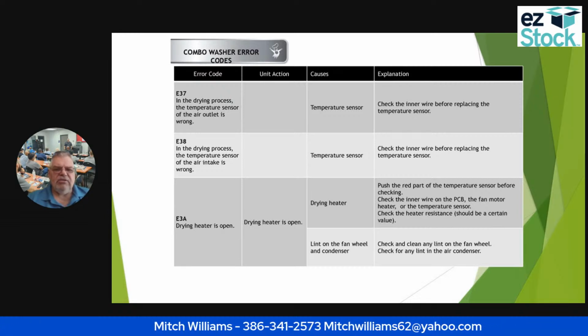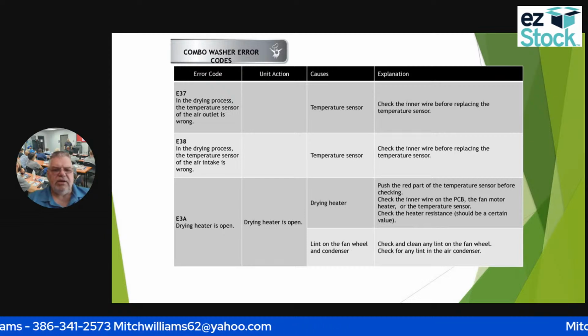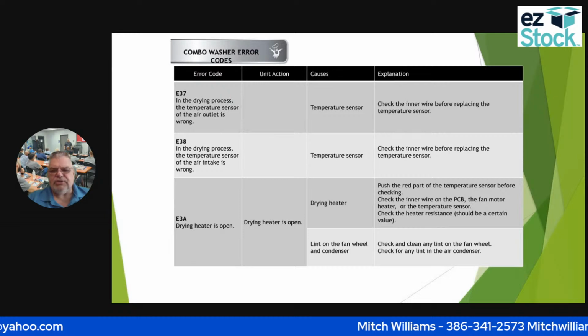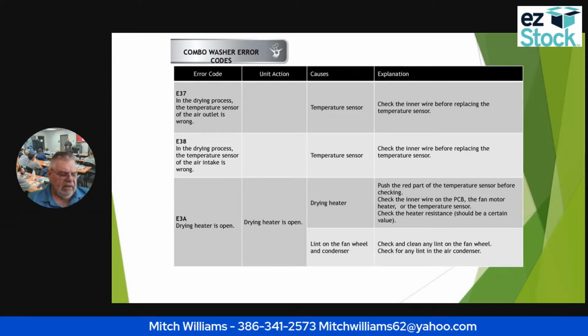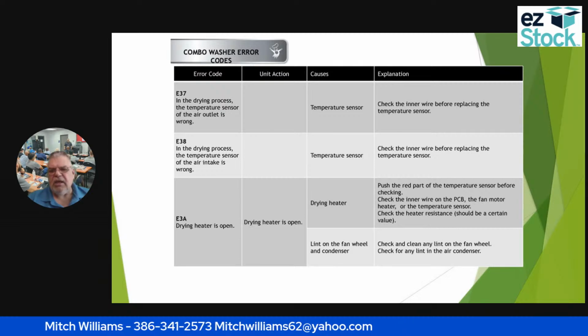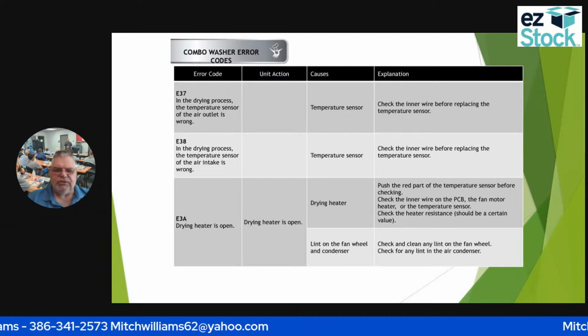So if I have an E38, it says in the drying process, the temperature sensor in the air intake is wrong. So I'm going to have to check that air temperature sensor again. I'm going to check the wire, and then if I find that that's okay, I'm going to have to replace the sensor itself.